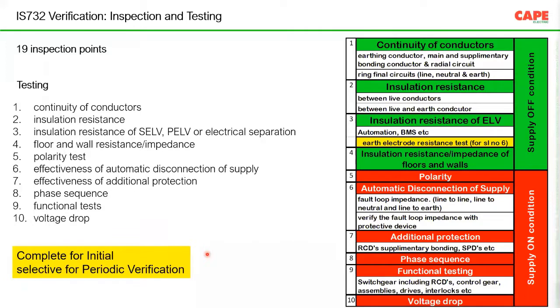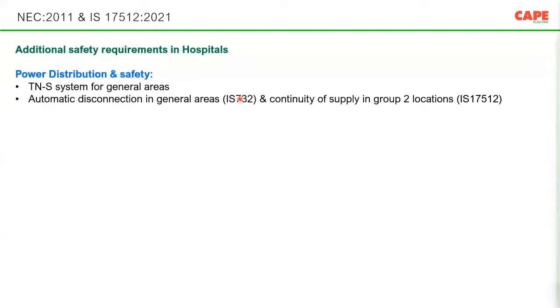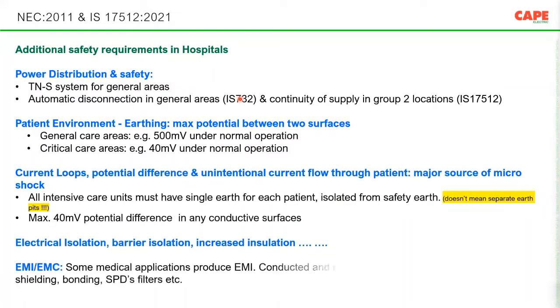And the final part is testing. In any hospital, the testing recommended in IS 732 for general locations is very much mandatory. There are 19 inspection points and about 10 tests. Of course, there is one more, called PAT, the portable appliance test. These tests are very much mandatory. And for the medical location, as I said, additional safety features are required, such as a TNS system being mandatory. That means the person doing the testing should understand what TNS is, and should check and find out the integrity of the TNS system.